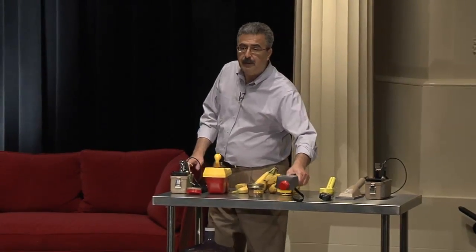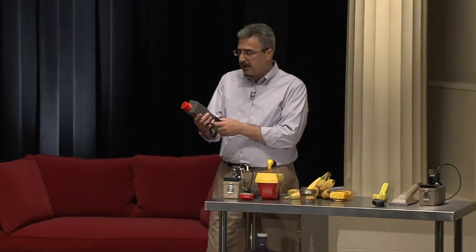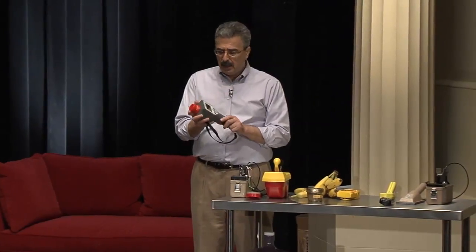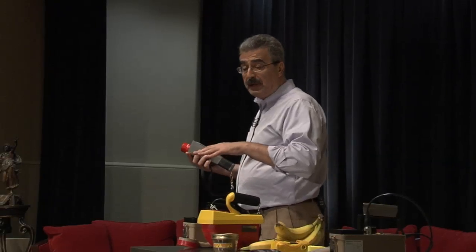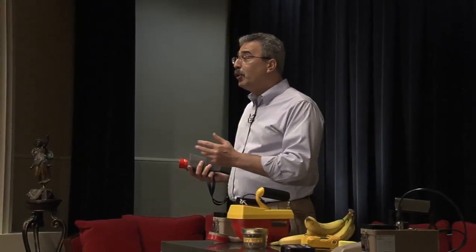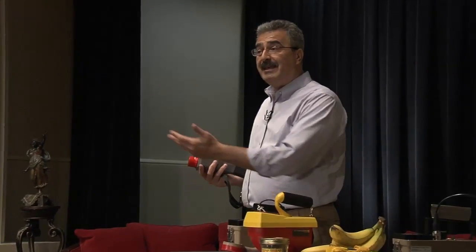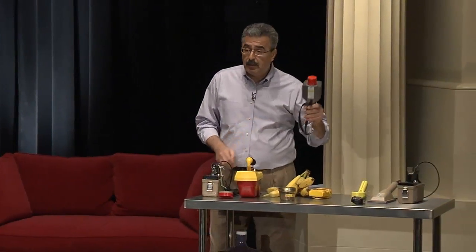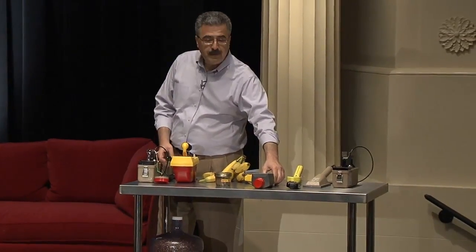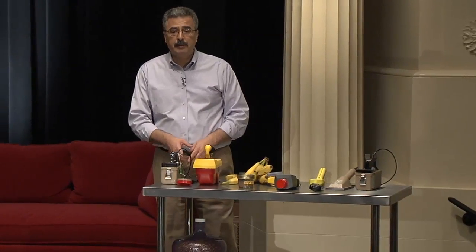Another instrument that's very useful for first responders is this one. This is called an isotope identifier. And again, there are different brands and models of these types of instruments. Remember, for the earlier ones we can tell if it's alpha or beta, but we don't know what radionuclide. If you have a gamma-emitting radionuclide in the environment, some kind of an incident, this instrument will allow identification of those radionuclides. So we can tell it's cesium, or what type of radionuclide it is. Again, that's valuable information to get in the field for responders.